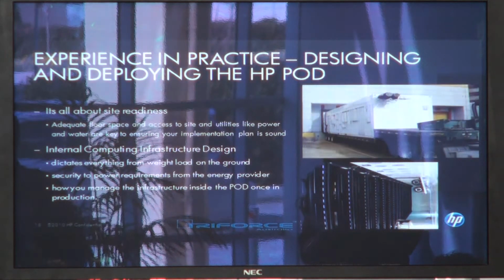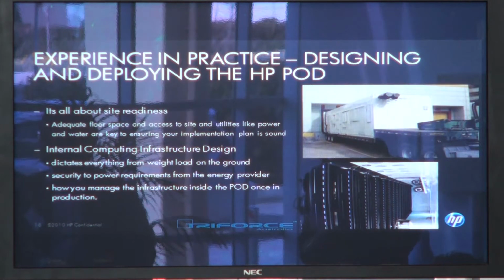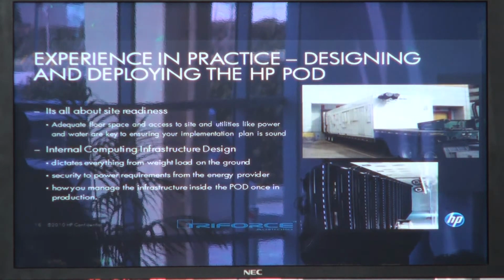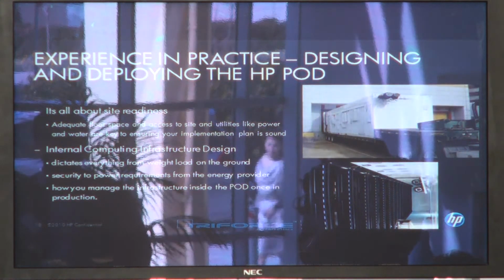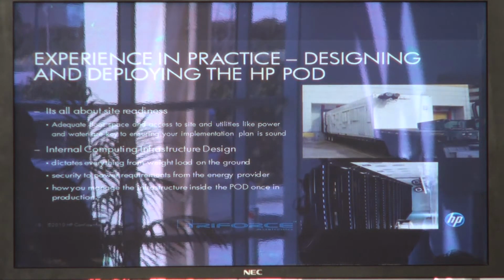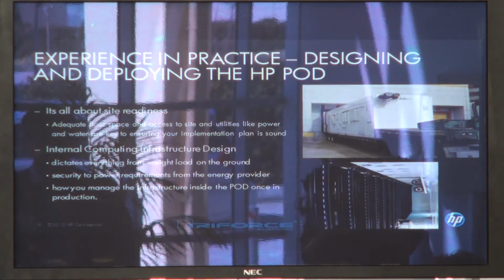From an internal computing infrastructure point of view, we'll touch on this again when we walk through the pod, but there's little consideration apart from it fitting into a 19-inch rack. The way the PUE rating on this pod is achieved is by isolating the cold aisle and the hot aisle, making sure you're as efficient as possible, always serving cold air to something that actually needs it, not to the general area as most data centers in Australia do.